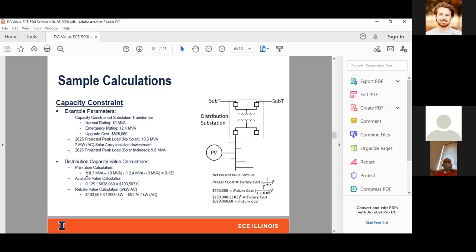The multiplier, or the proration calculation, is the delta of the normal rating to the forecasted loading, divided by that ratio of emergency to normal. So you have a multiplier of 0.125. If we multiply that by the upgrade cost that the utility would have spent at that location, you get $103,000 as the value at that specific location for a 2 megawatt solar. If you break that down to a per kW basis, you're looking at $51 and change per kW at that specific location.